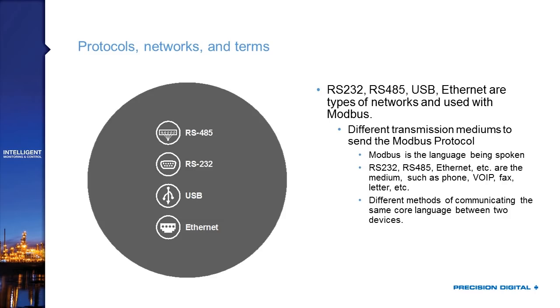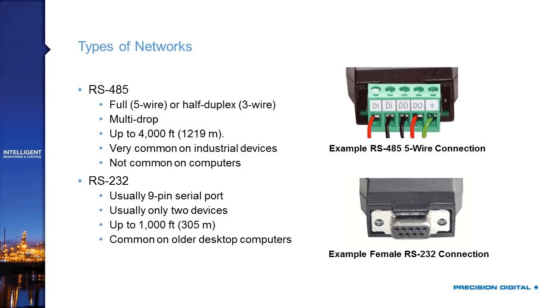RS-485 is the most common network type on serial Modbus devices. It comes in 5-wire and 3-wire options — you can wire a 5-wire device to a 3-wire device, but you need to know which you're dealing with in advance. RS-485 is a multi-drop network, meaning you can have multiple devices wired in parallel across the same lines. It can travel quite far — up to 4,000 feet for most applications.